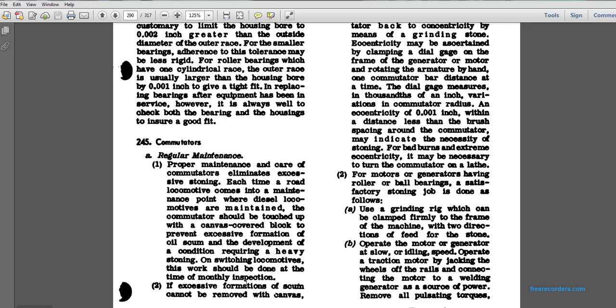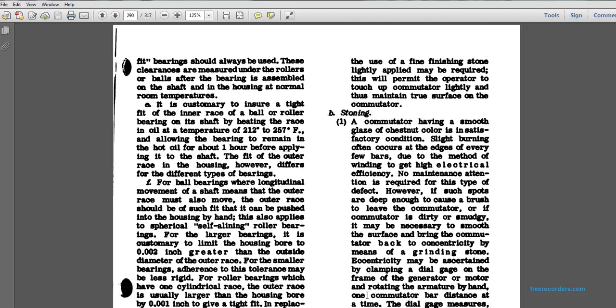If excessive formations of scum cannot be removed with the canvas, the use of a fine finishing stone lightly applied may be required. This will permit the operator to touch up the commutator lightly and maintain a true surface on the commutator. Stoning. A commutator may have a smooth glaze of chestnut color in a satisfactory condition. Slight burning often occurs at the edges of every few bars due to the method of winding to get high electrical efficiency. No maintenance attention is required for this type of defect.